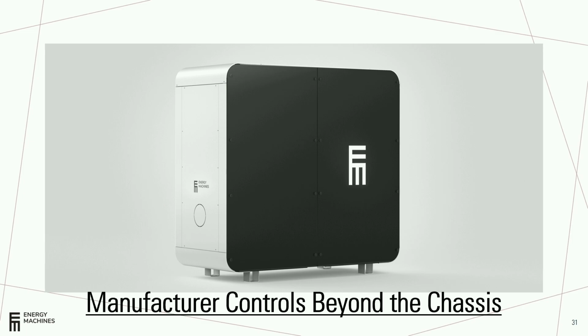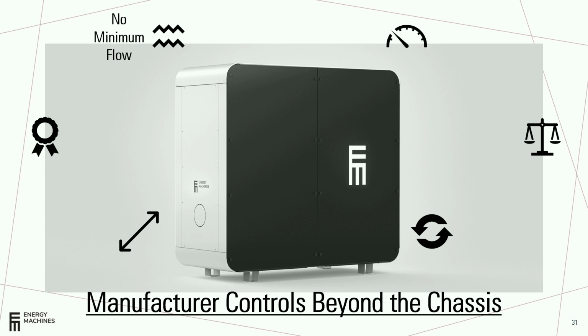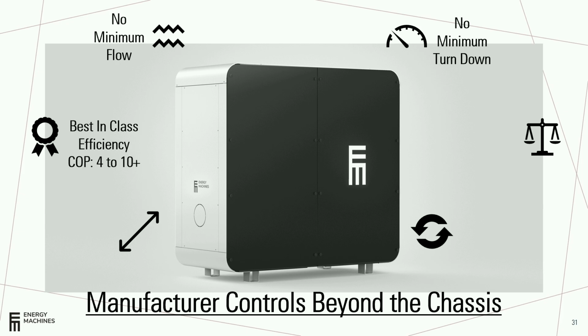So here's what you also get with controls that extend beyond just the chassis, right? If you can extend the manufacturer controls into the mechanical room, you get a lot of superpowers, if you will. For example, there's no minimum flow in the machines or in the system design. The machine itself has limitations, but the system design has no minimum flow, no minimum turndown. You can get COPs on the low end, and this is for the 180 degree, while also hitting your chilled water set points in excess of 4. And on your lower temperature conditions, you can easily get into double digits, some of them even getting into the teens. You have a self-balancing system.